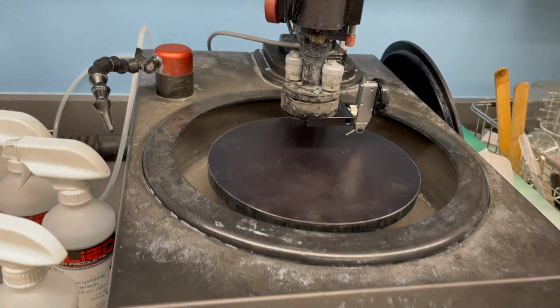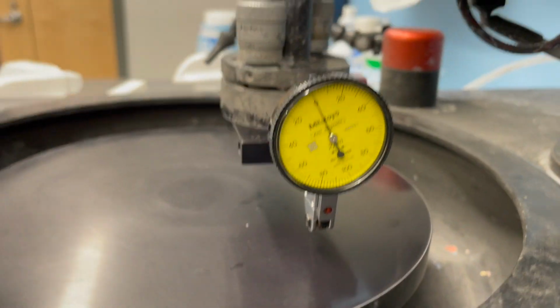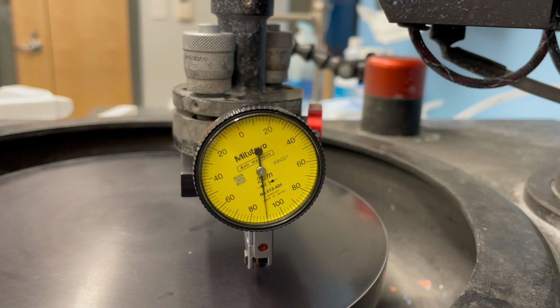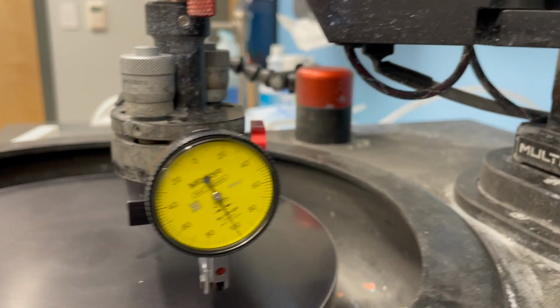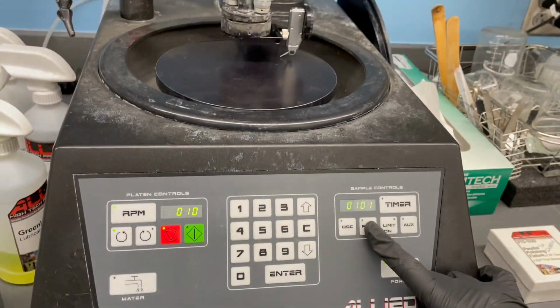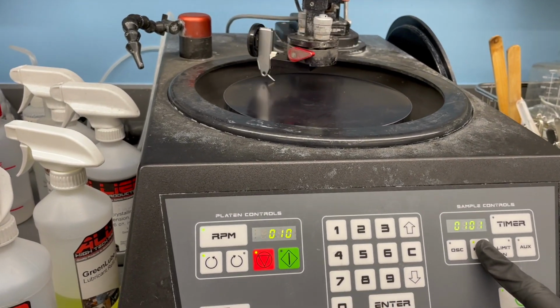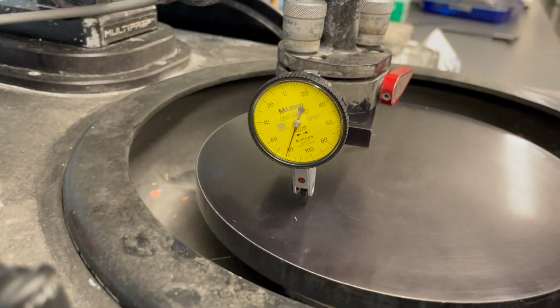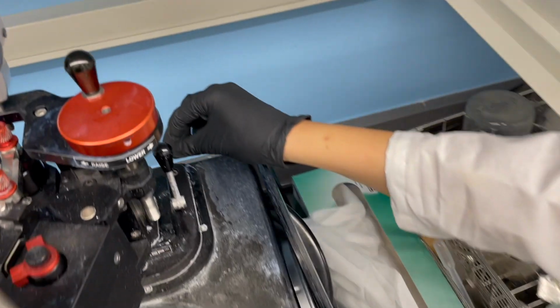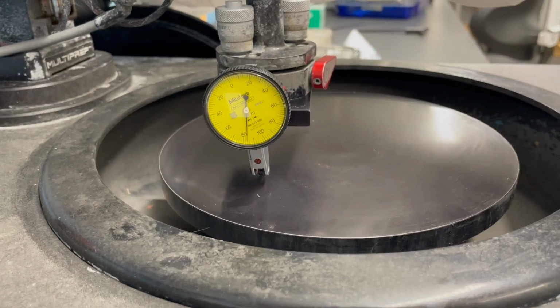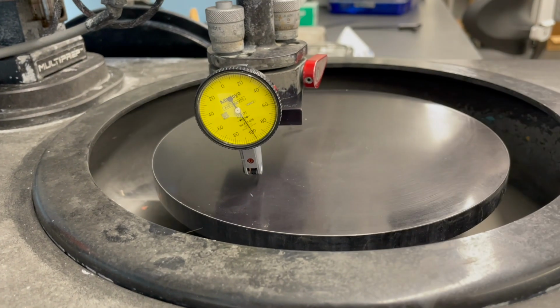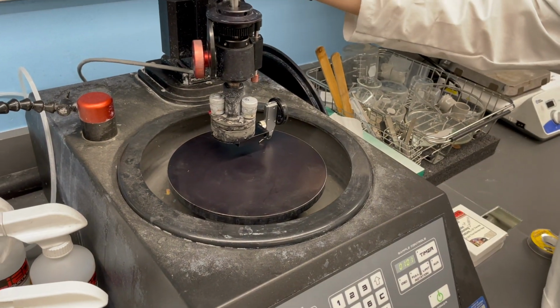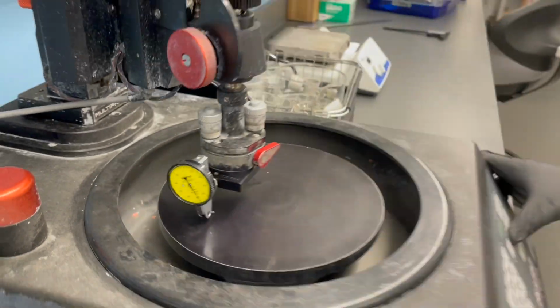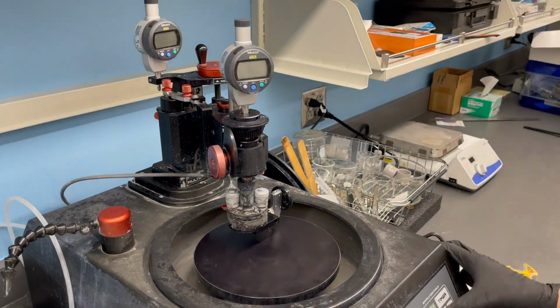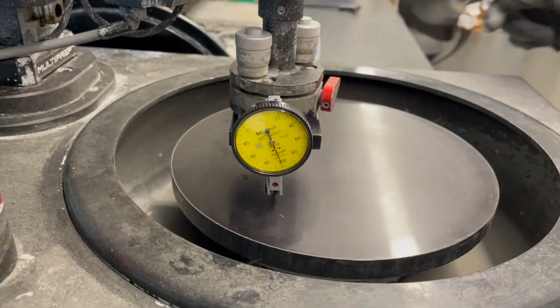Use the full button to rotate the dial to 3 o'clock. Lower the arm so that the dial reads 100. Then, press the full button again to rotate the dial to 9 o'clock. Now we will make adjustments to the dial to bring it back to 100. Use the proper Allen wrench to adjust the back right bolt until the dial reads 100. Press the full button again to rotate the dial back to the 3 o'clock position, and repeat at 3 and 9 o'clock until no additional adjustments are required and the dial stays within 2 step sizes of 100.